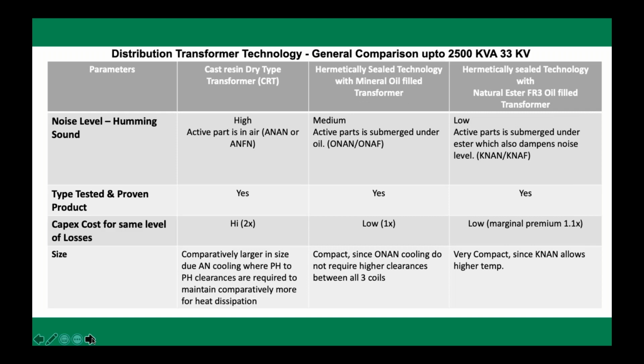And last but not least is which we really do not care much, but noise level. In Europe recently, there has been a million euro penalty to one of the company because they were installing noisy transformer beside somebody's house. And then he was getting annoyed because the transformer is always making a humming noise, like something like that. And that is a result of none other than the noisy transformers. Because dry type transformers are ventilated, and the NEMA standard also allows more noise into the transformers, and it doesn't have any dampening device because air is a carrier and not the dampening device.